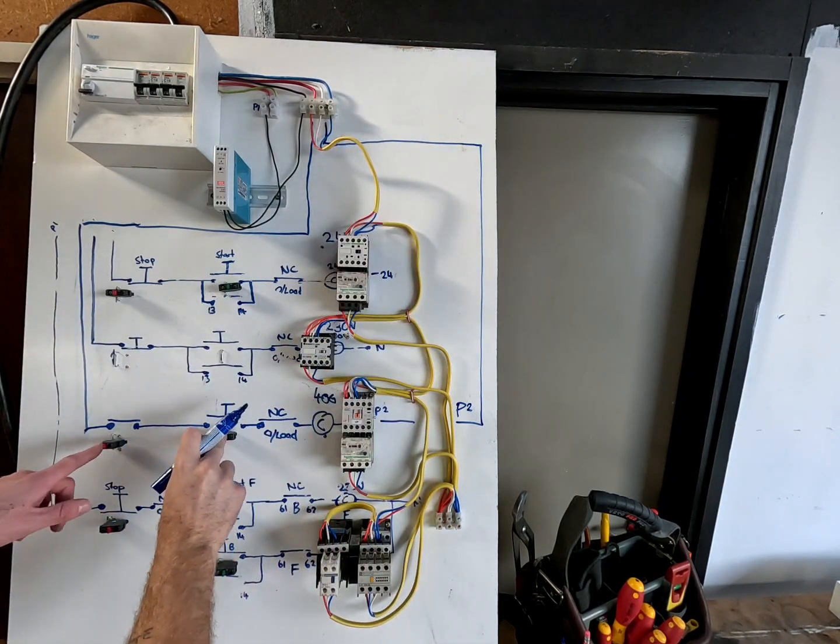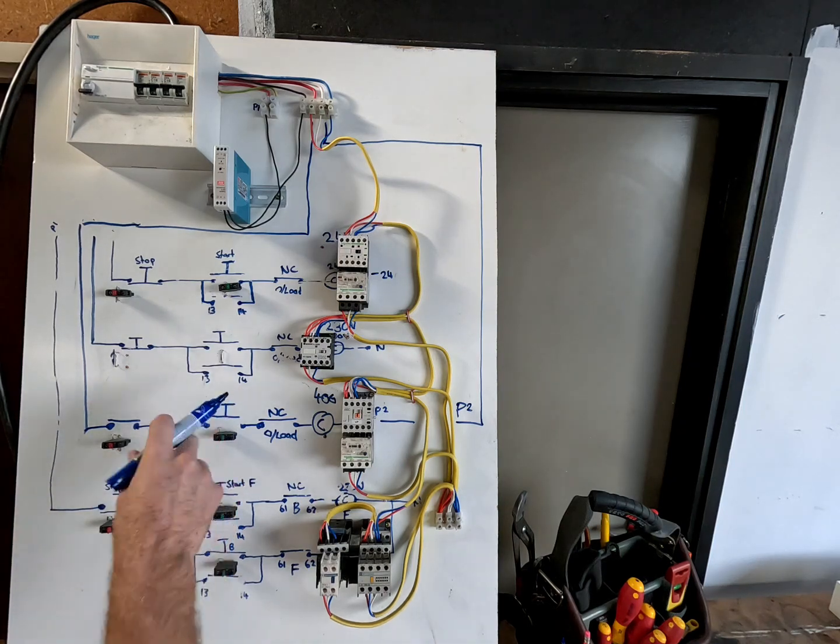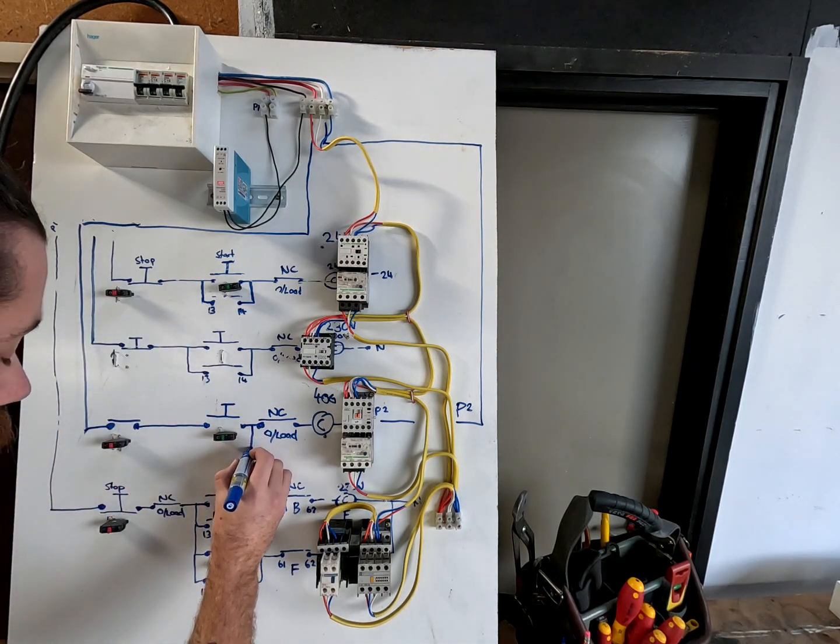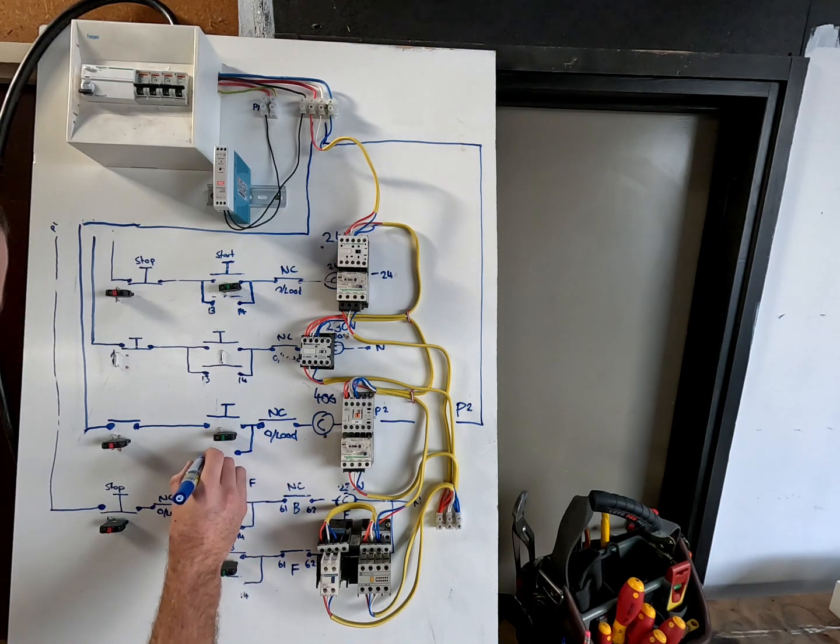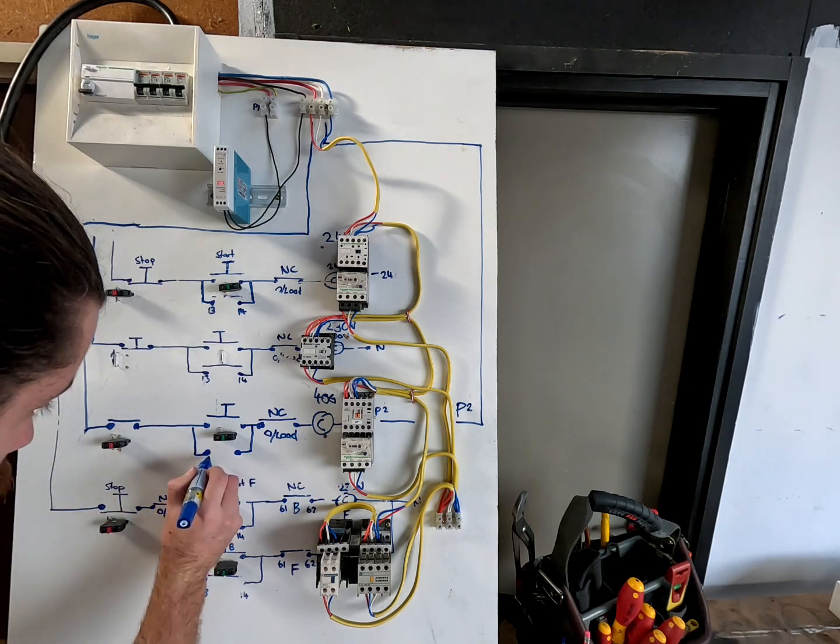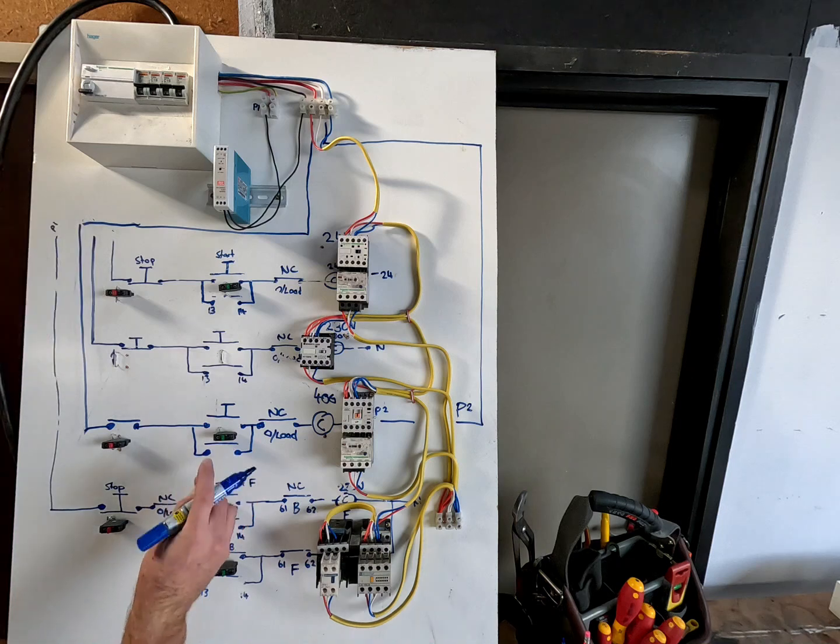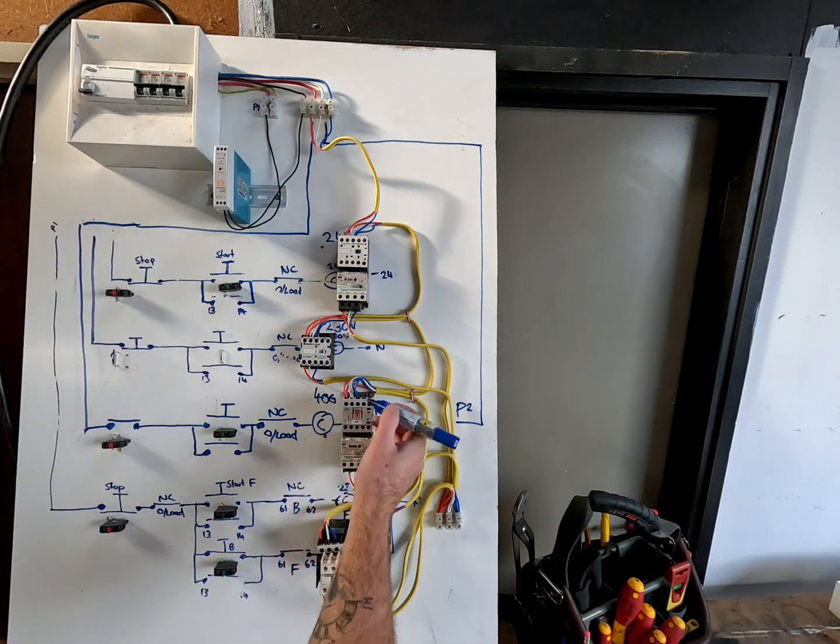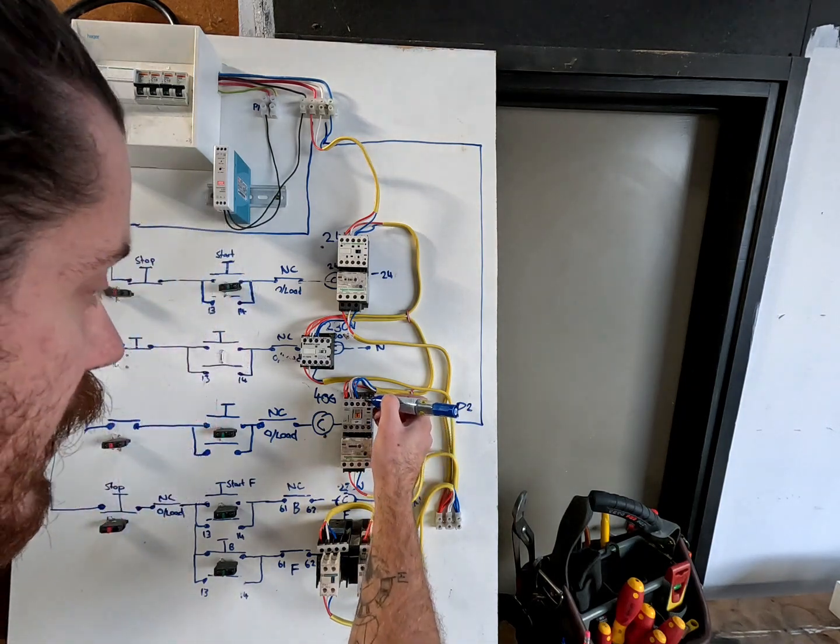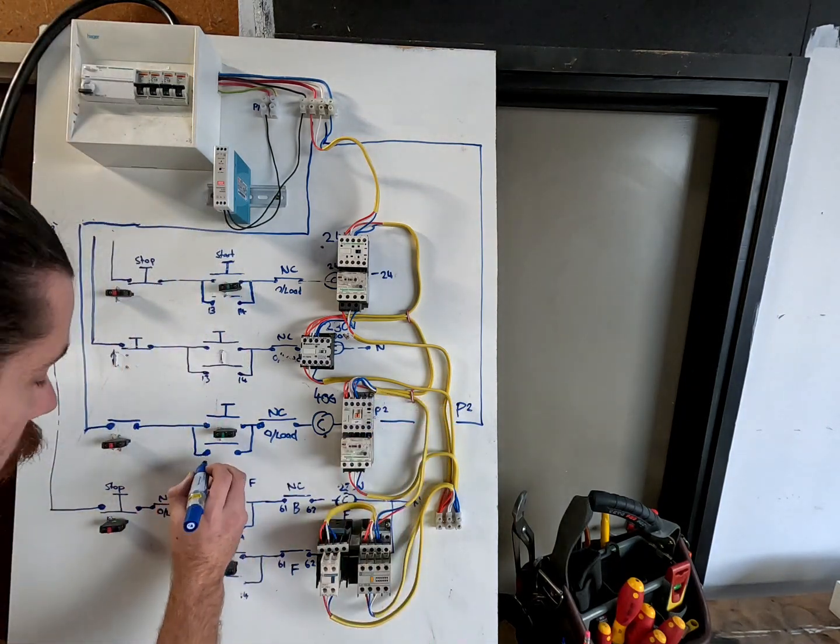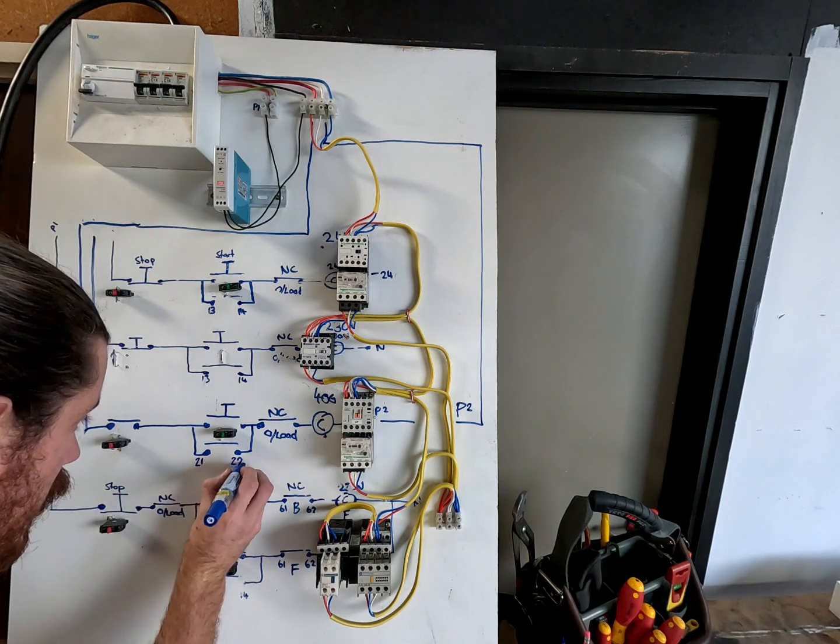Remember, this wouldn't hold it on unless you press the button and held it, so we've got to put in our latch which is in parallel. Remember, start buttons are in parallel, stop buttons are in series. Now this is also a normally open. This is 13 and 14 on the contactor. On this contactor it's actually 21 and 22, so we'll write 21 and 22.